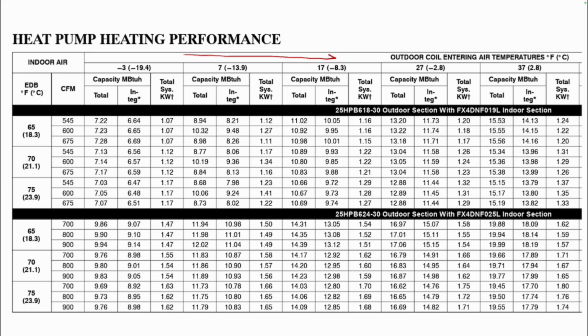This one's laid out slightly different. First off, we still have outdoor air temperature across the top, but this one goes from low temperature and increases to the right, where earlier we were high temperature and decreasing to the right. Let's look at this one for 17 degrees. Then on the left in this vertical column, we have entering dry bulb temperature: 65, 70, and 75. Let's go with 70.